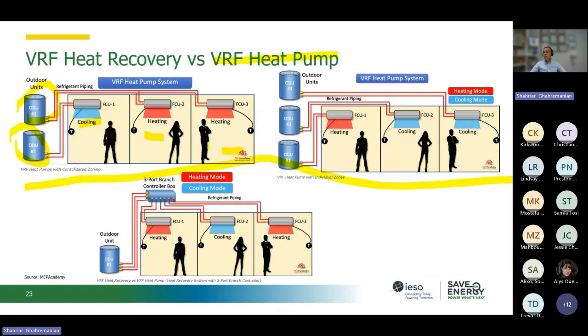If we want to give that independence, then we need to have three different outdoor units for the heat pump, and then they can decide what they want. The hospital is a good example of this kind of application. Schools are another one actually, because some areas of the school may heat up, so they need to cool down actually. But outside it is winter season, so that's a good case to consider. But technology is actually here to save us, and there are VRF heat recovery heat pumps, and basically they have a 3-port branch controller box, which means that we are going to have only one outdoor unit, and this outdoor unit is connected to this branch controller box, and depending on the load of each area, it can provide heating and cooling at the same time actually.